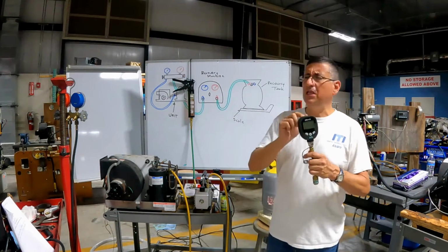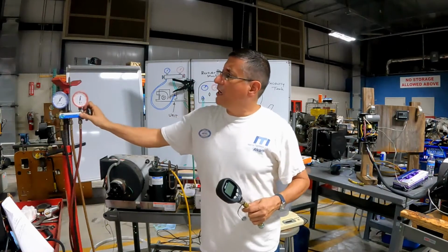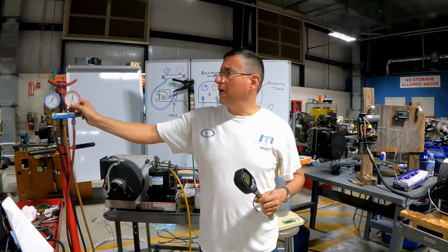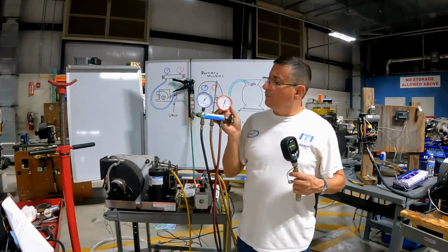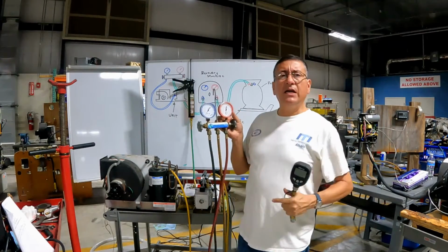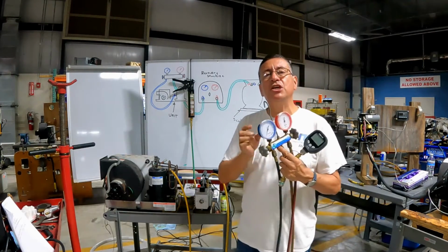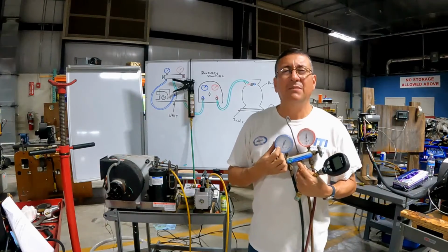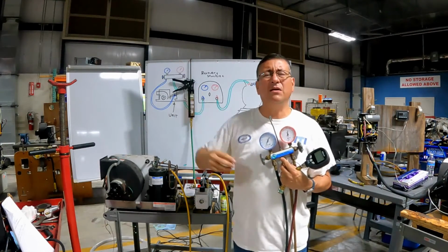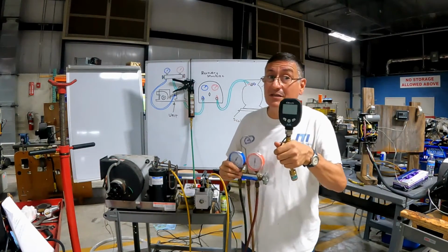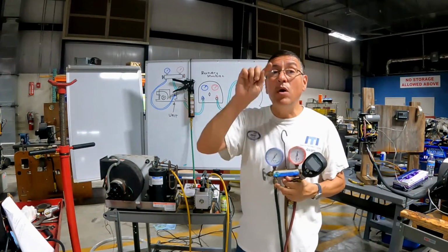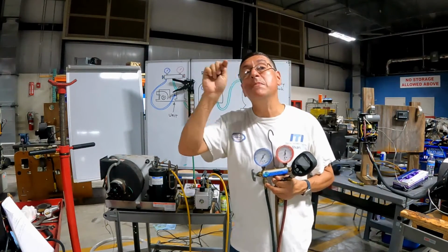No, Mr. Lopez, I don't need that. I am going to read with the gauge of my set. With this gauge, I can read. No, my friend, because this gauge is in PSI. PSI is a large measurement. This is microns. It's microns. It's one divided by one million.